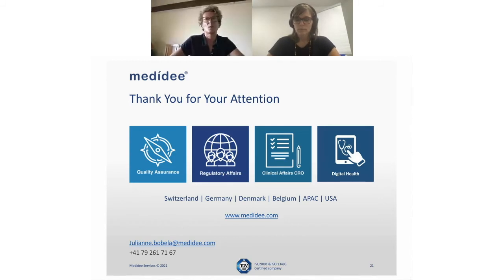So I will try to take this one, Julian. Indeed, for some analytes, there's no such certified reference. So then we have to find another way of measuring and assessing the analytical performance of the device. One way to go is to use spiked samples, meaning that you spike samples, such as if your device is intended for serum, you will spike serum samples which should be negative for your analyte, with known concentrations of the analyte, which is purified, if possible, or you measure the analyte by another method.